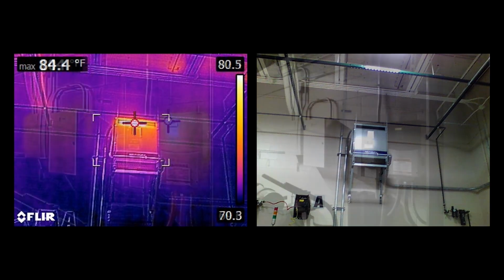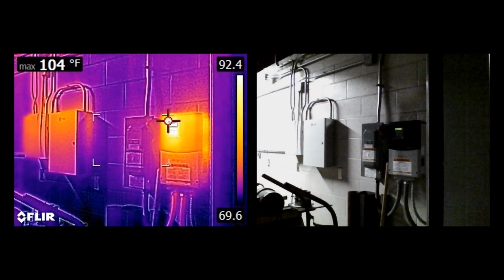This shot taken on the wall of control equipment highlights something worth bringing up. The VFD we are pointing out on the right has a temperature of 104 in that area, so that's fairly warm. Is it warmer than it should be? Through our troubleshooting experience, we'll find out. Also, the other thing we can see from the regular picture is the light, possibly sunlight, shining against the wall towards the left. So the elevated temperature we see in the control boxes to the left may not be in the box, but may be a function of sunlight shining on the box and warming it up.